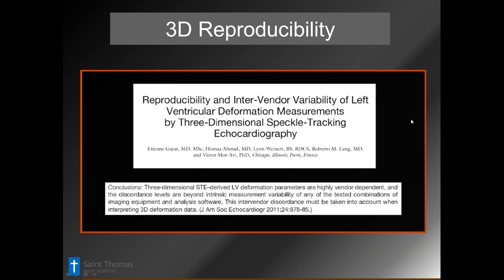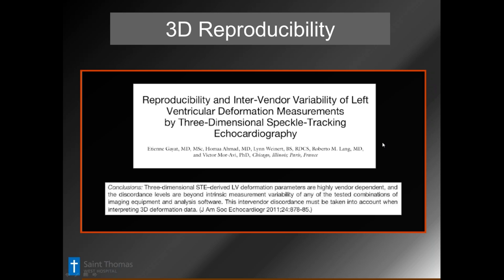There are some questions about 3D reproducibility. A good paper from the Chicago team discussed 3D speckle tracking — the speckle tracking method used mathematically for automatic tracing, which we can then edit. They found some parameters are vendor-dependent and that inter-vendor discordance has to be taken into account. To decrease analysis subjectivity center-to-center and operator-to-operator, we either use an identical cart or vendor-independent software for analysis. We actually have both: one brand of cart with their 3D volumetrics on the cart, and the TomTec LVA on our workstation.